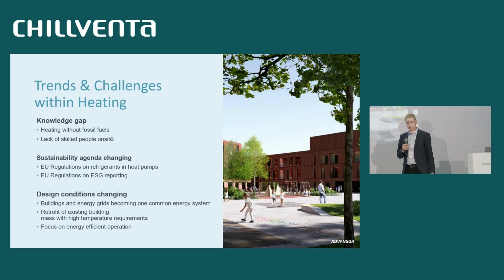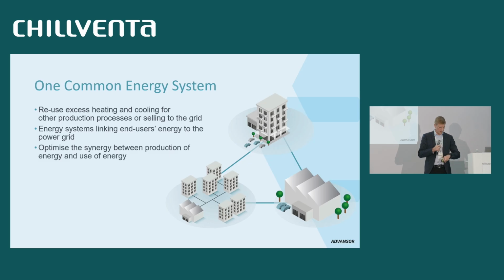Then the design conditions are changing. So we see that buildings and energy grids become more one common system. And when we look at the temperature profiles and the building mass, then of course on new buildings, new areas, we have underfloor heating. We can have a low supply temperature. But if we're looking at the existing building mass, all the old buildings require quite a high supply temperature. And then of course, when we talk about heat pumps, there's also a focus on energy efficiency, also energy efficient operation. I will come back to that. So, the design conditions changing.